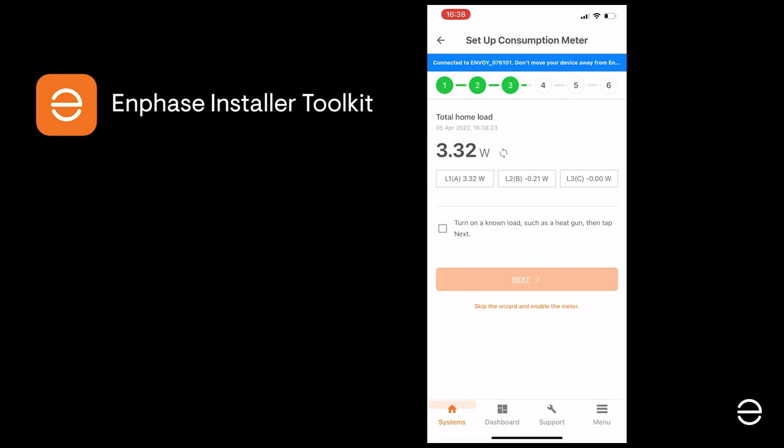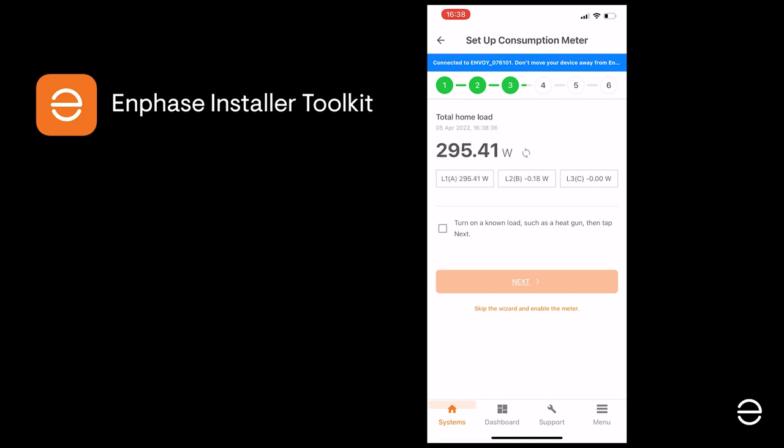Now we're going to add a significant known load, such as a heat gun for example, to check if the CTs are measuring correctly. When we plug in a known load, as you can see here, the load builds up to what we would expect. If the load does correspond to what you would expect for your installation, click on Next.